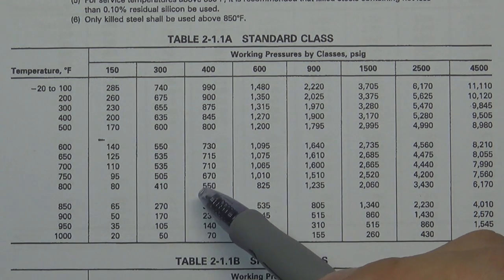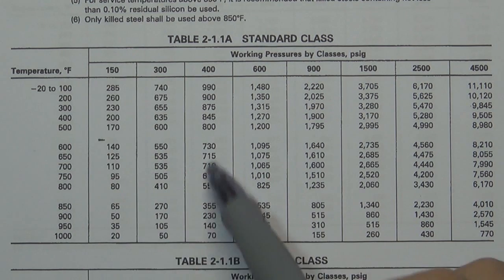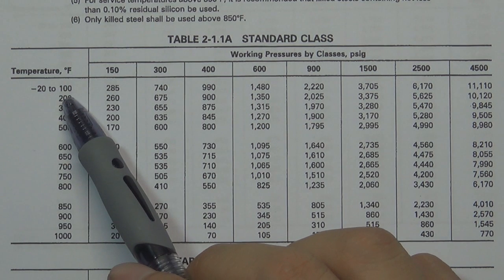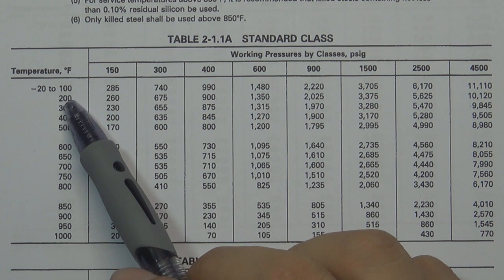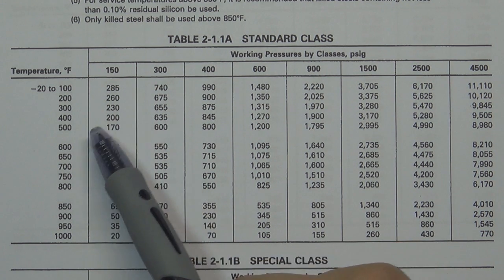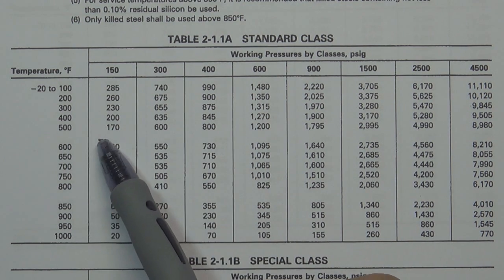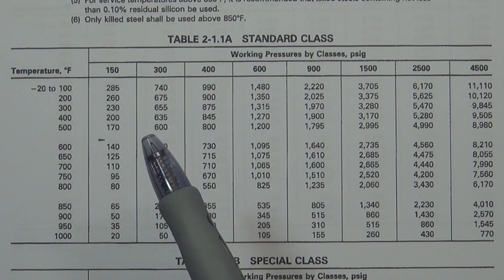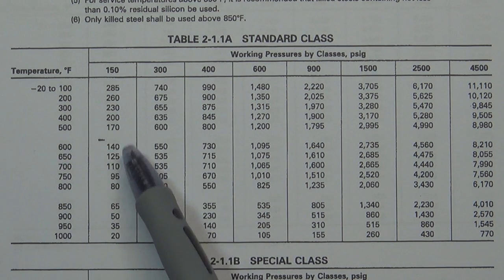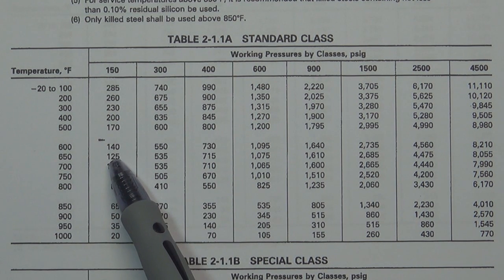For example, if you have a valve made of WCB with class 150, you can use this table to check how much pressure it can hold. At 100°F working temperature, this valve can hold 285 PSI. When the temperature rises to 500°F, the valve can only hold 170 PSI. And at 600°F, it can only hold 140 PSI.